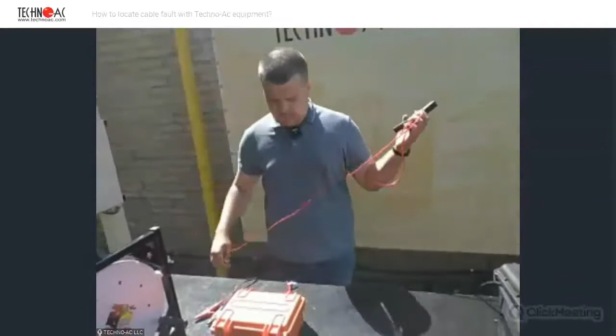Let me recap a little bit the information about electromagnetic cable fault location. You have to use the DKI or DODK sensor in order to locate short circuits or cable faults. You can locate cable faults at the whole supported depth of the receiver. For AP 19.1, it is 10 meters. For AP 27, it is 6 meters. So you can pinpoint the location. The accuracy of this device is plus minus 10 to 15 centimeters, which means that you can locate the fault pretty accurately.